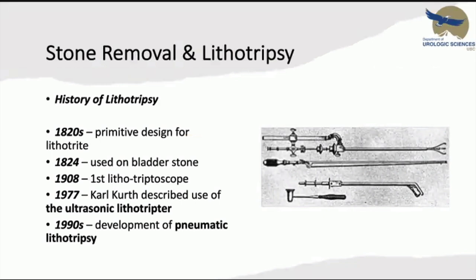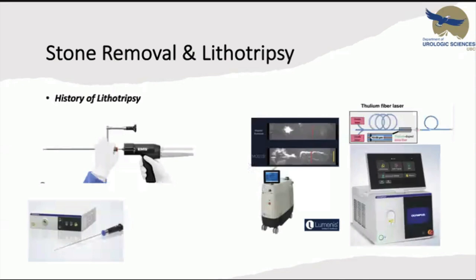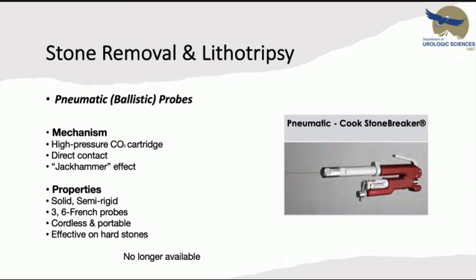Moving to stone removal and lithotripsy: ultrasonic lithotripsy was first described in 1977, pneumatic lithotripsy in the 1990s. Now we have many different devices and technologies to fragment stones. Pneumatic probes use high-pressure CO2 cartridges, need direct contact, and deliver a jackhammer effect. They have three to six French probes, are cordless and portable.